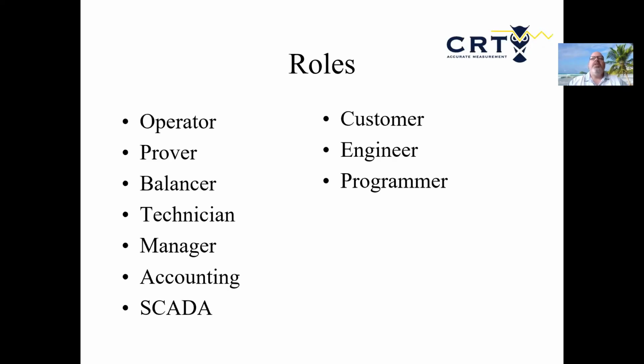A balancer comes into the flow computer and pulls out reports to verify the data, balancing pipeline systems or the accounting system volumes that are recorded. Or they see an error in the system and need to get into the flow computer to figure out why, going back to look at the audit trail to figure out, oh, we lost temperature, now we need to make a change.